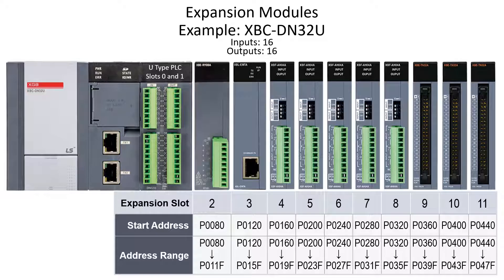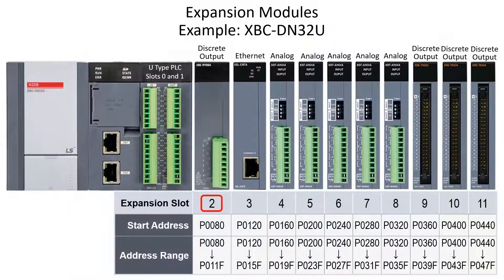In this example we are using a 16-input, 16-output model configured with 10 expansion modules. A total of 10 expansion modules can be added to the U-type PLC. Slot 2 is the first expansion slot in the U-type configuration. Slot 1 is reserved for the internal functions within the U-type PLC.